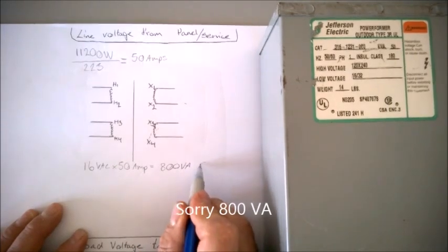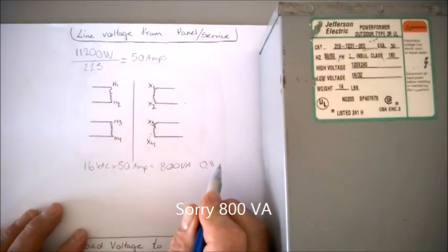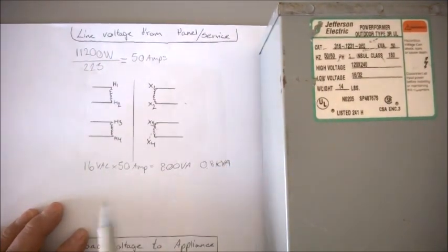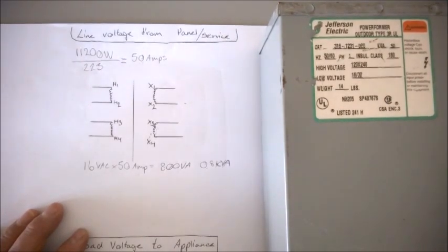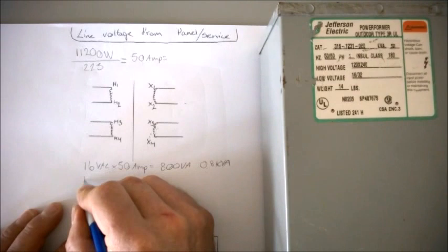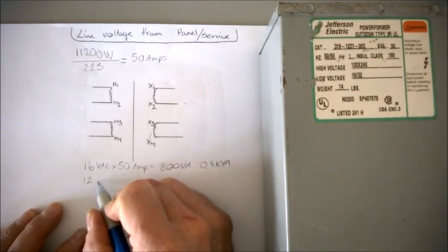That's equal to 0.8 KVA, because kilo means 1000. So for a 50 amp load and we want to boost with 16 volts or buck with 16 volts, you need a 1.0 KVA buck booster. Let's see here what happens. Let's say it was a 12/24 booster and we only wanted to boost or buck with 12 volts.